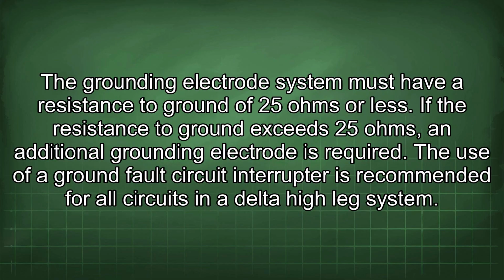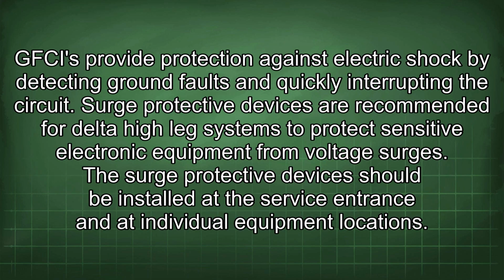The grounding electrode system must have a resistance to ground of 25 ohms or less. If the resistance to ground exceeds 25 ohms, an additional grounding electrode is required. The use of a ground fault circuit interrupter is recommended for all circuits in a delta high leg system. GFCIs provide protection against electric shock by detecting ground faults and quickly interrupting the circuit. Surge protective devices are recommended for delta high leg systems to protect sensitive electronic equipment from voltage surges. The surge protective devices should be installed at the service entrance and at individual equipment locations.